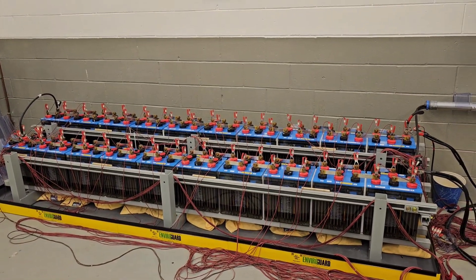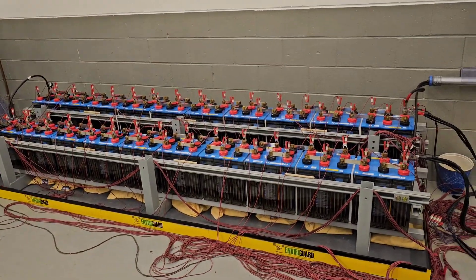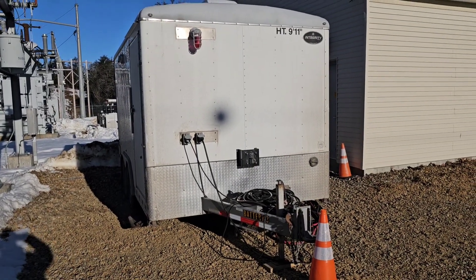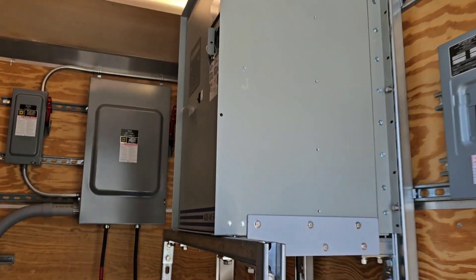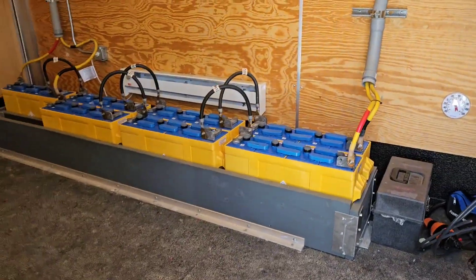To make sure the batteries would function correctly in the event of a power outage, we have to really draw them down — but to do that we have to disconnect them from the substation. We use that disconnect panel right there. So how do we do that? We use a battery trailer — it's just a mobile trailer with its own charger, disconnect, and a set of batteries meant to travel over the road: locomotive batteries.